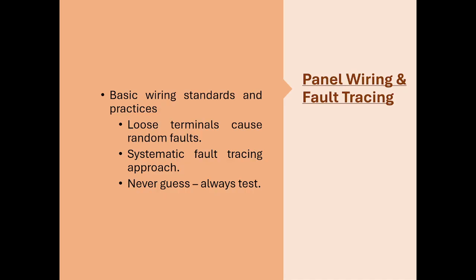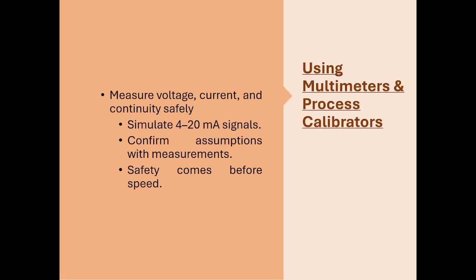So to do this safely, engineers rely on measurement tools. On the next slide, we're going to look at some measurement tools like the multimeters and the process calibrators. A multimeter is a basic electrical tool used to measure voltage, current, and continuity. It tells you whether power is present and whether connections are intact. Okay, a process calibrator is used mainly in instrumentation, and it can simulate signals like the 4 to 20 milliamp that I mentioned earlier, so you can test systems without disturbing the actual process. Now, these tools remove assumptions, they help you confirm reality, and always remember, safety comes before speed.